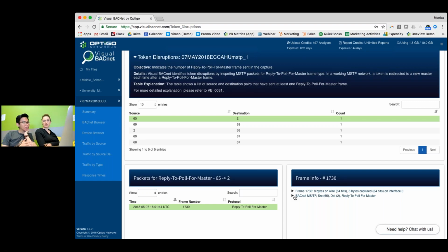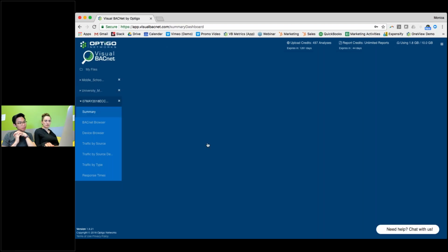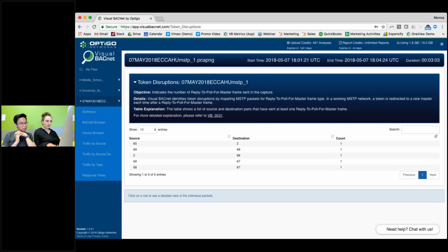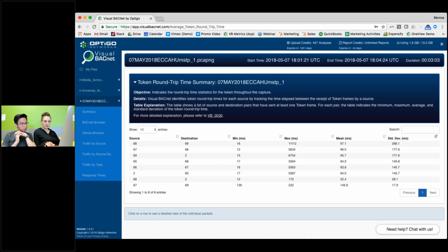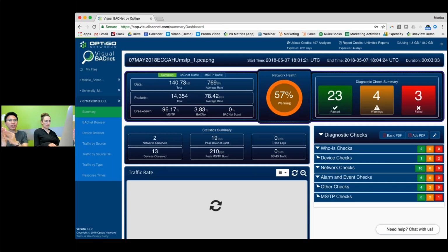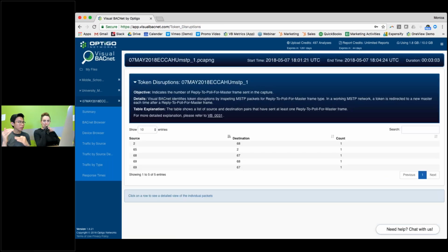But did 65 come online during the capture? It didn't look like it. Because I think 2 was sending to 65 the whole time. So if 2 knows 65 is the next master, 65 shouldn't be responding. He's the master. Right, 2 should just be sending. Okay, so 2 is the main controller.